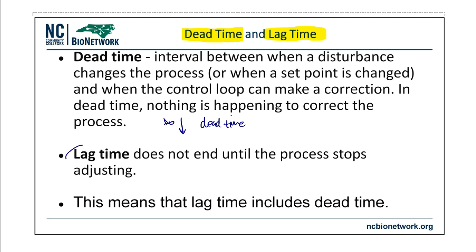So that is what lag time is. It includes the dead time, because that's the time that it took for the controller to recognize something needs to be fixed. And it's also going to include what I would call the action time. That action time is for that valve to open. That action time is going to include that fluid coming in. That action time is going to include, well, now that we're getting the fluid, how fast is it going to be before we get back to the appropriate levels, in this case of dissolved oxygen, that we need in that bioreactor. So all of that is time that is very important, and it is the entire thing.